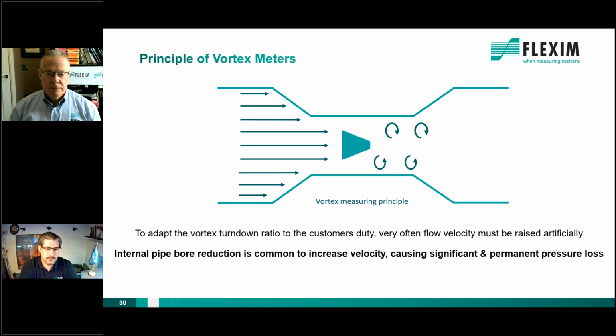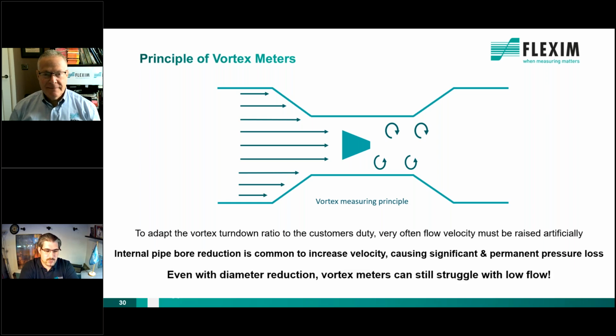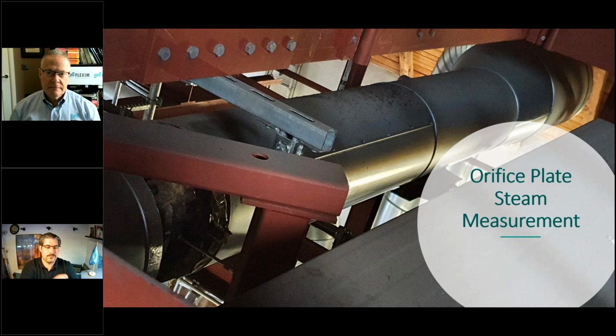So what you need to do is artificially raise your flow velocity by reducing the pipe diameter. And this is very common for vortex meters, that you have this for one built into the meter's body, or even have additional pipe diameter reductions in your steam system. So what you're going to do is, you want to save energy. You're installing a measurement by reducing the pipe diameter, increasing your pressure drop, and need more energy to overcome this pressure drop. So this is quite not a good idea, I guess. But an even bigger problem here, even with those pipe diameter reductions, is that those vortex meters and also the orifice plates, the differential pressure meters, still struggle with low flow. So if you are on low demand, you will have problems measuring your steam flow.